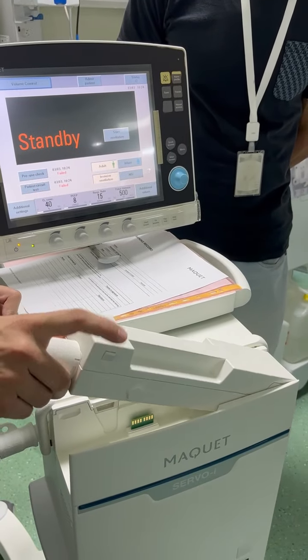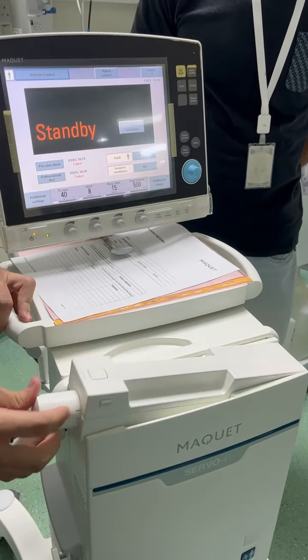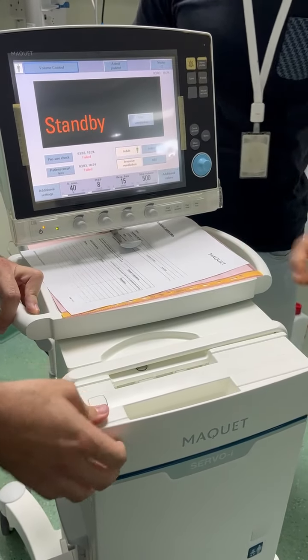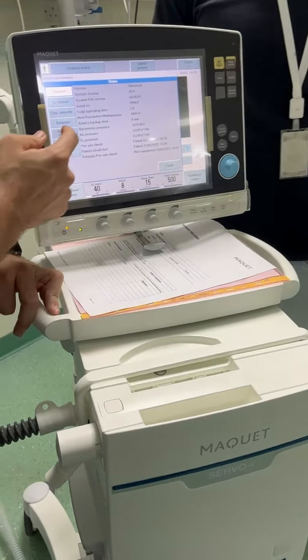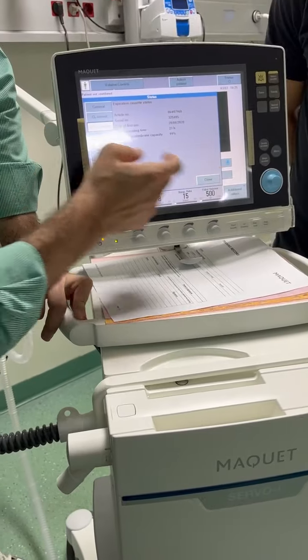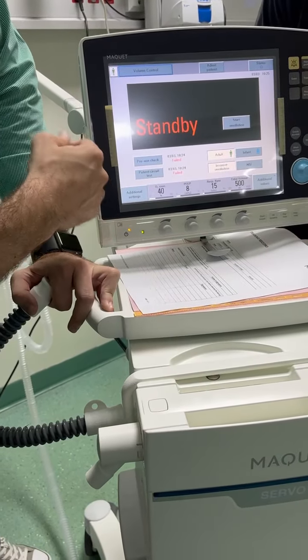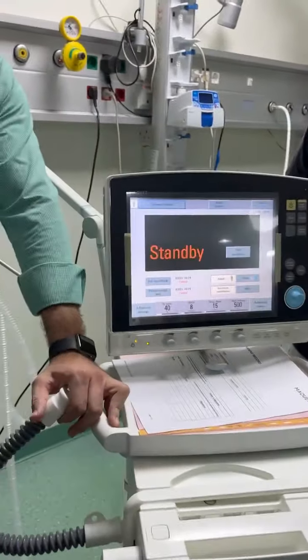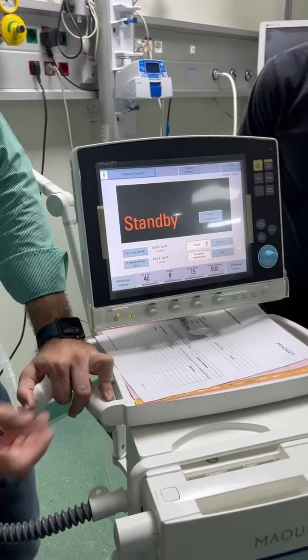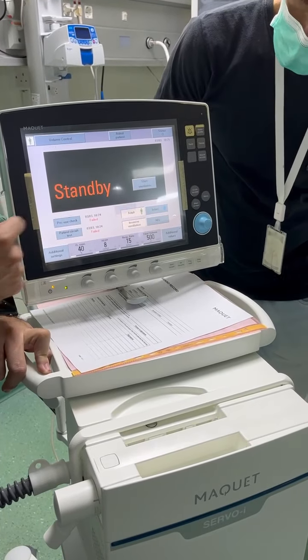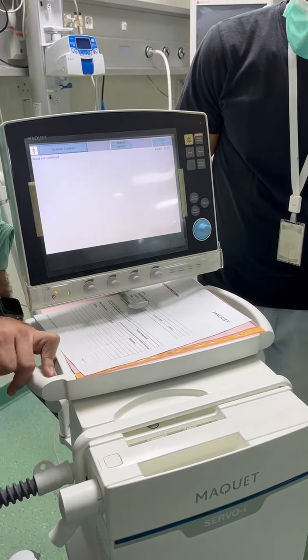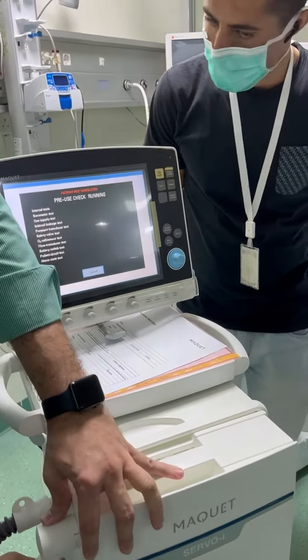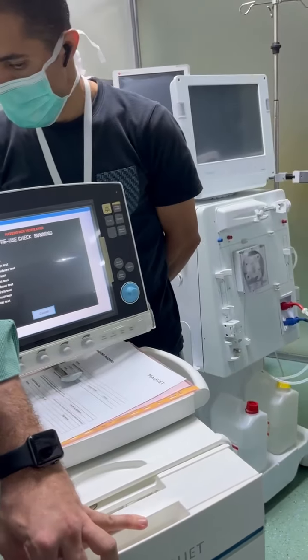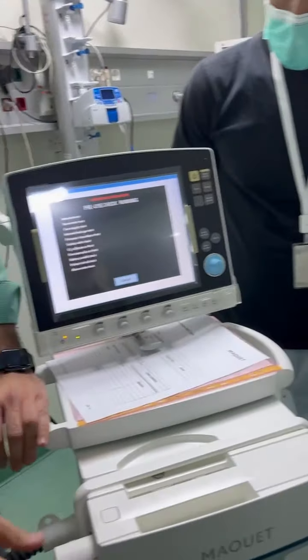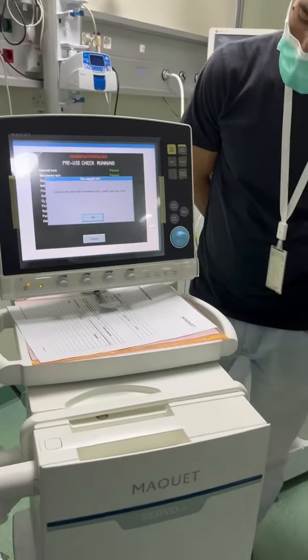Of course, when you remove it, it will detect that the expiratory cassette is disconnected. Let me check if it's detected. Right. In case something happened and I need to do the pre-use check again, I can click here on the pre-use check, because it will go through the same steps. We cannot calibrate this while the patient is on it, like the other ventilator. No. You should detach it from the patient, yes. Okay.